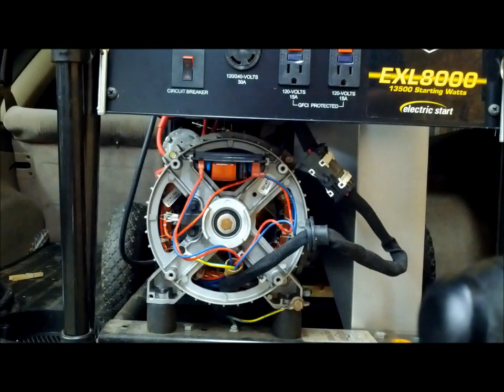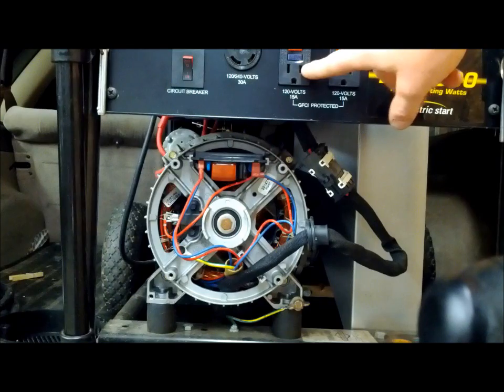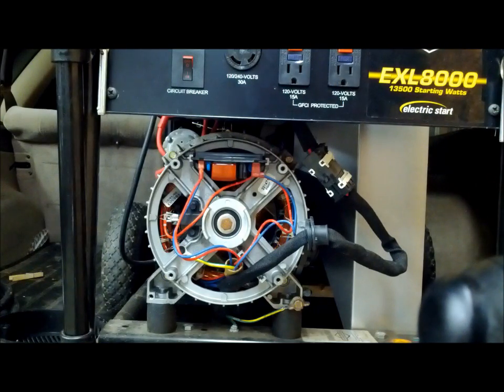You can watch my other video on how I tested the automatic voltage regulator, because that's also known as flashing the field, that will also restore that. If you don't want to do it that way, you can grab a corded drill, plug it into your 110 outlet, hold the trigger on, turn the chuck a couple times, and that should also restore it.